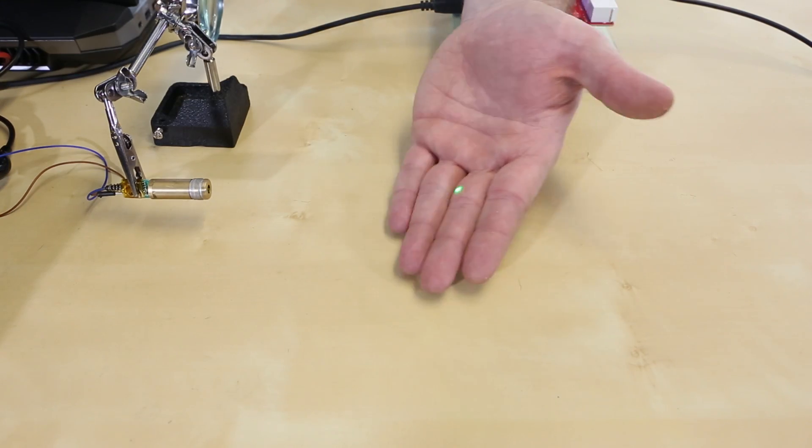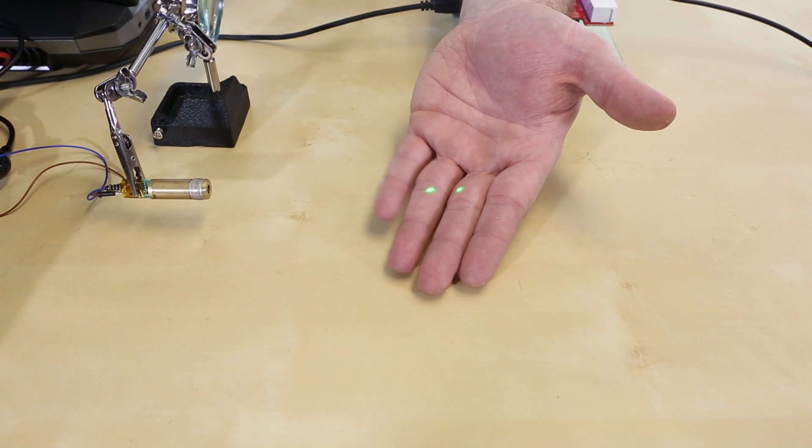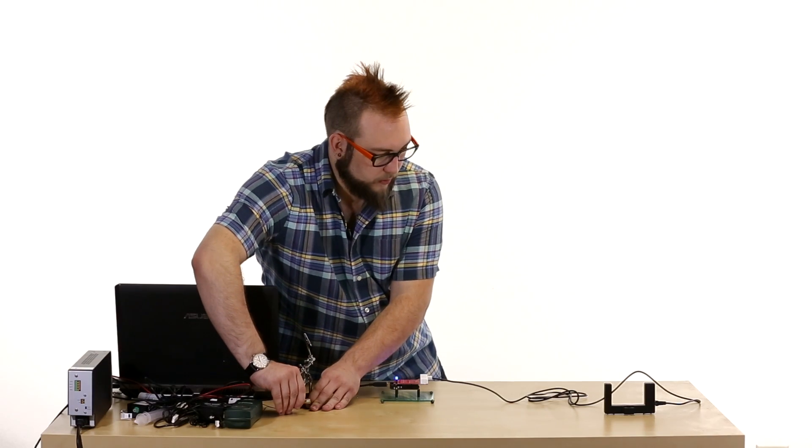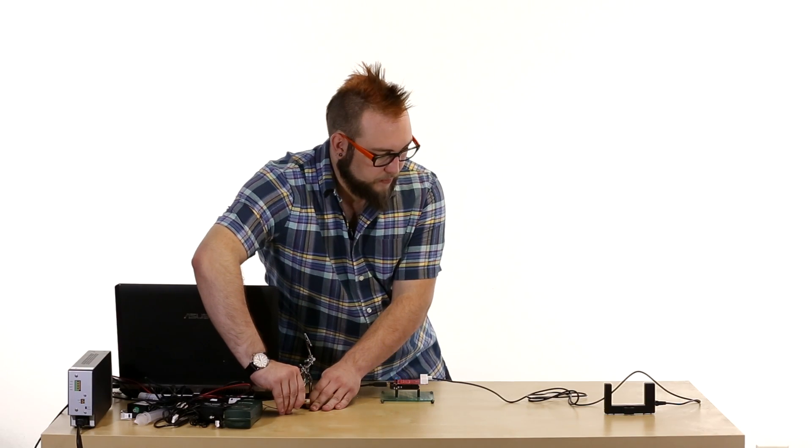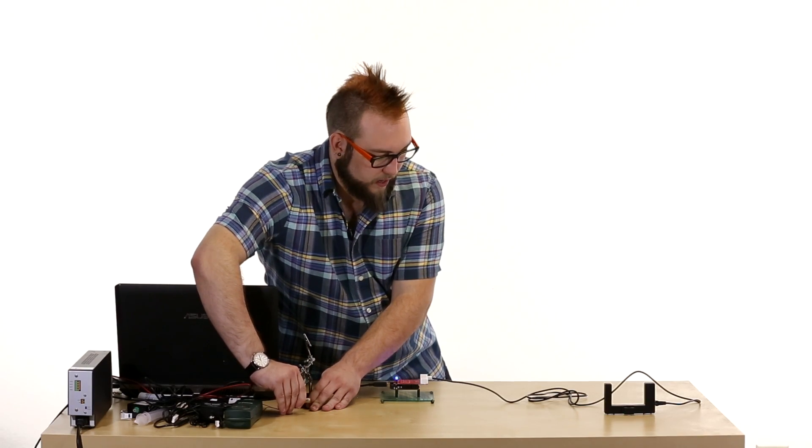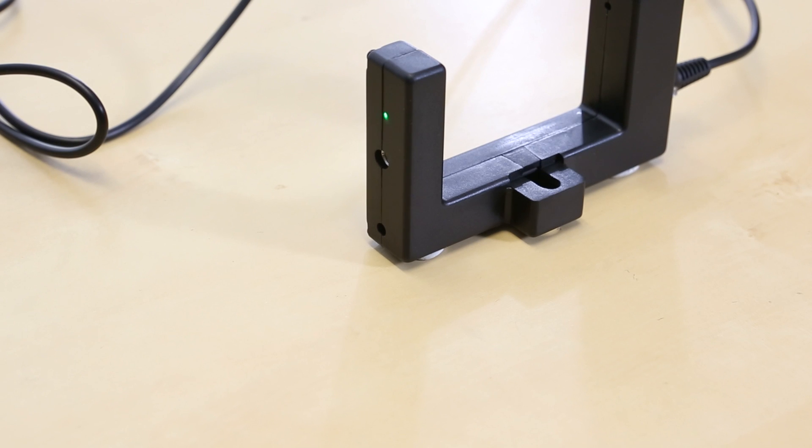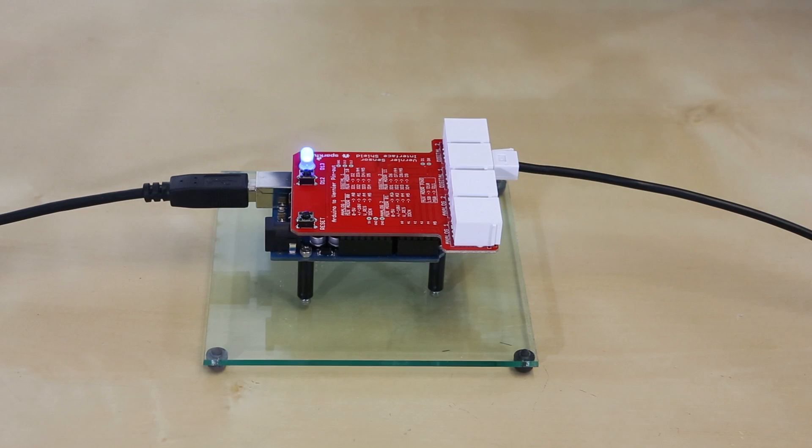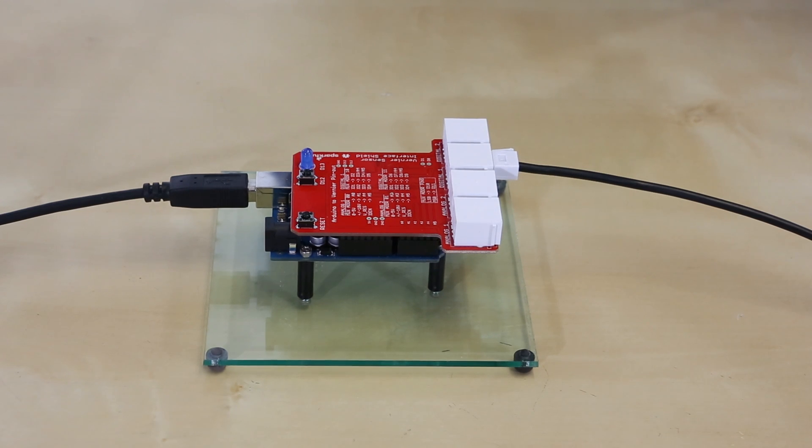So now all I have to do is turn on my power supply. And as you can see, there's a green laser dot here. And all you have to do is line up this laser dot with the detector. And when you get the laser dot lined up, you should see the light on the shield turn off to indicate that the beam is not being broken.